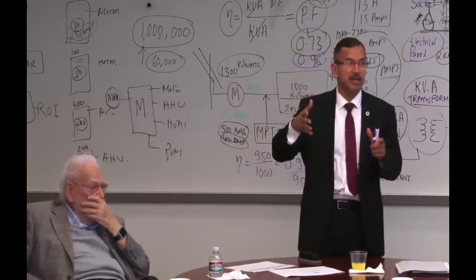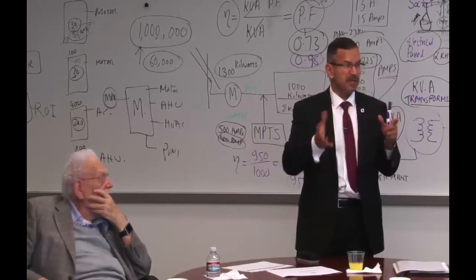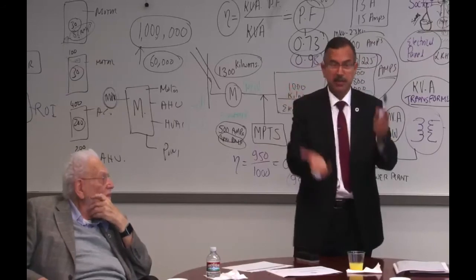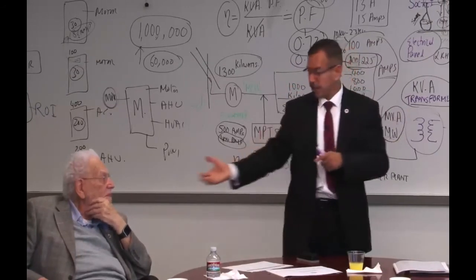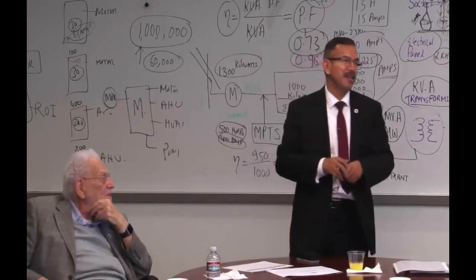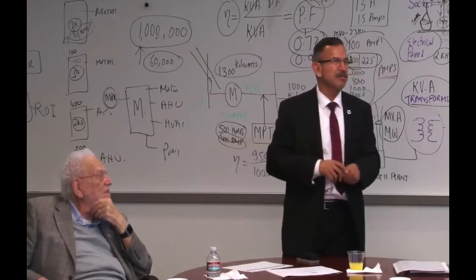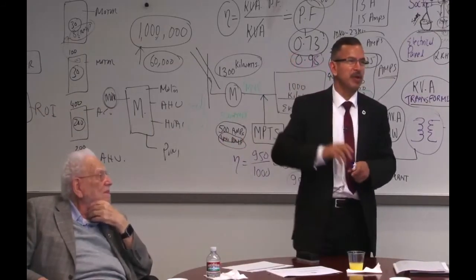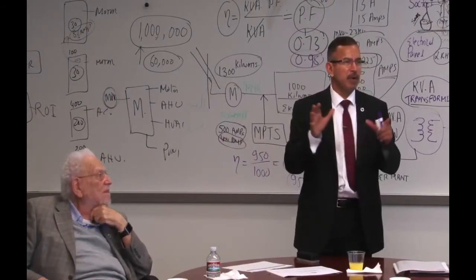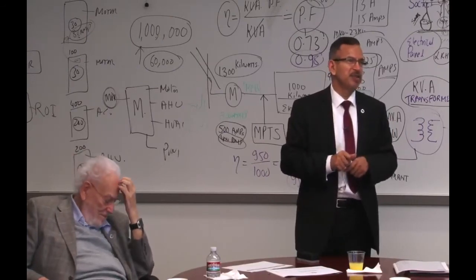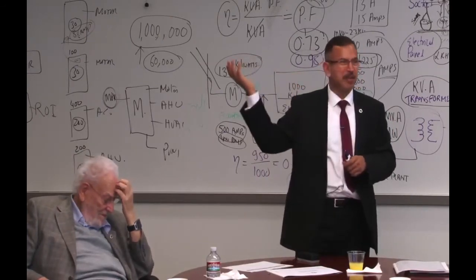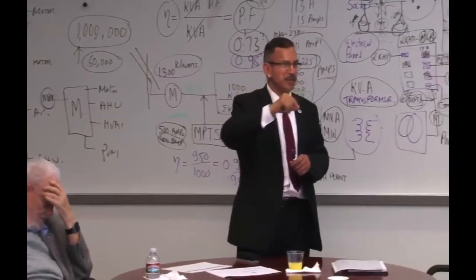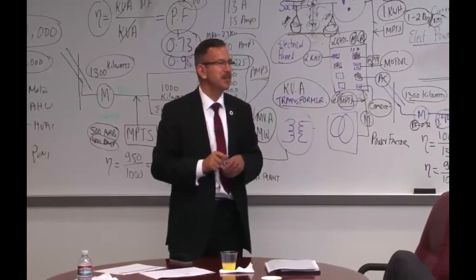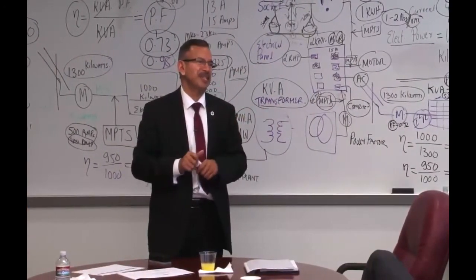Largest liquor store in the country, with a lot of freezers, compressors, lots of variations - compressors coming on and off. So we went and took permission to put it in. He said, you're wasting your time, I have done everything. He had spent $220,000 on a power conditioner to get to 0.90 on the main panel, because the utility had told him, you have to get to 0.90, you are a demand on my substation.